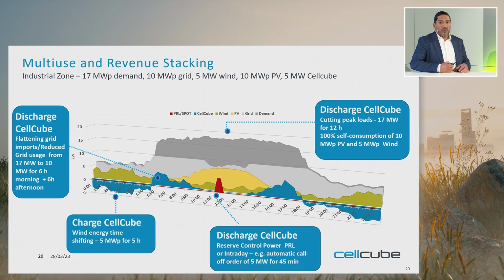In case there isn't, we charge from the wind and discharge during the day, just to help eliminate the peak power demand for longer periods. For example, we eliminate from 17 megawatts down to 10 megawatts - 7 megawatts reduction - during 11 hours, between 6 o'clock and 5 o'clock in the afternoon, when the industries in this zone are producing and activated.